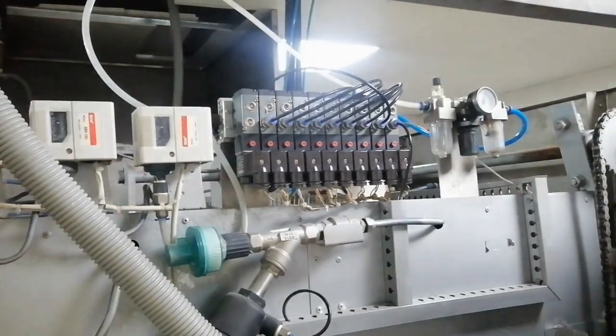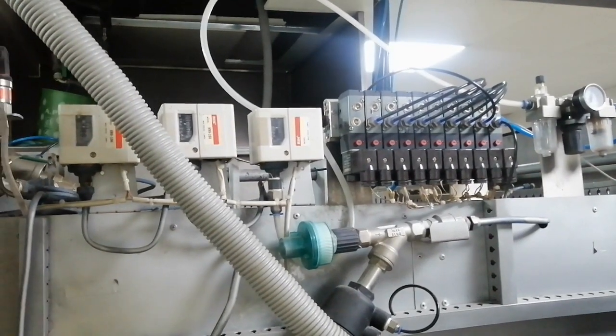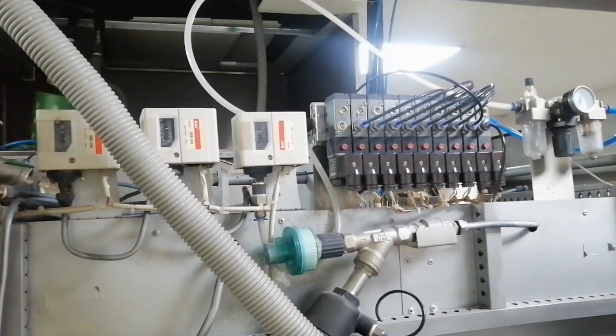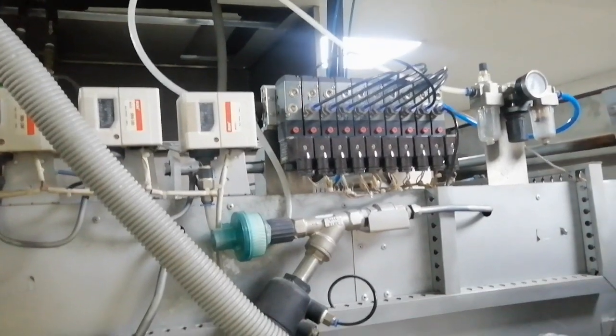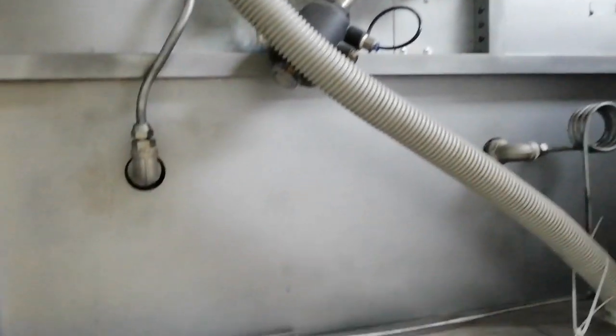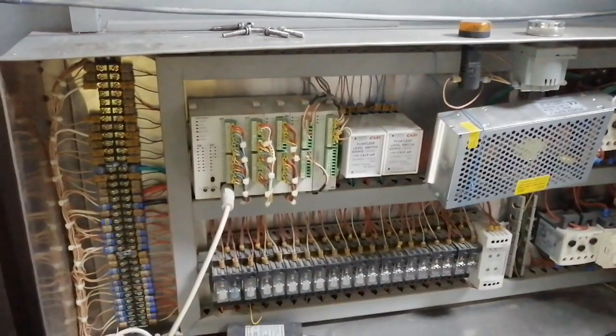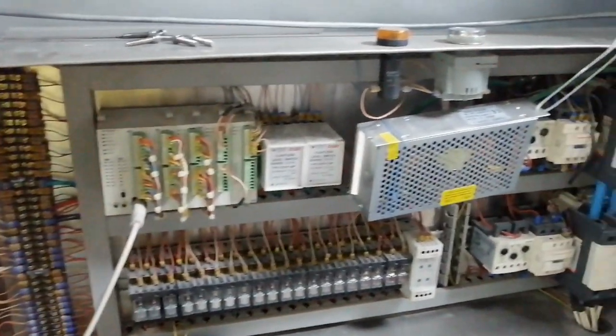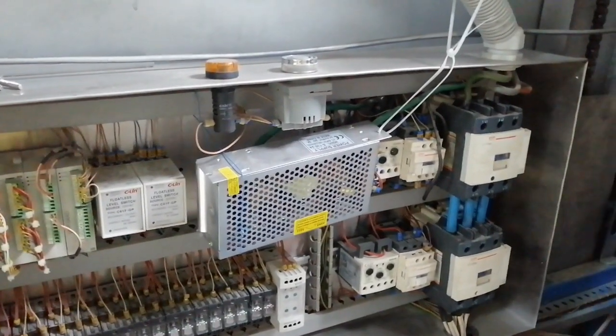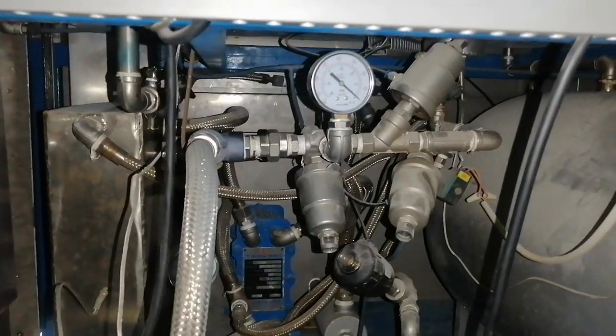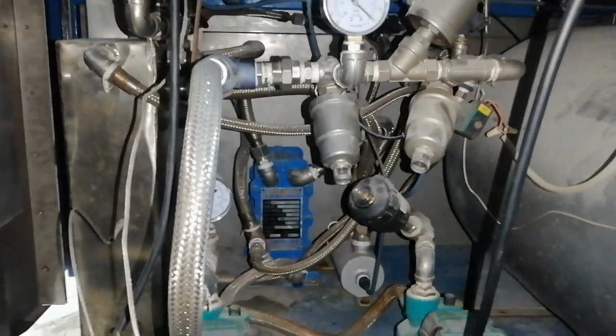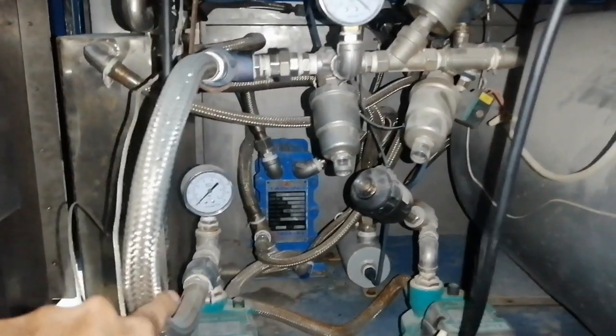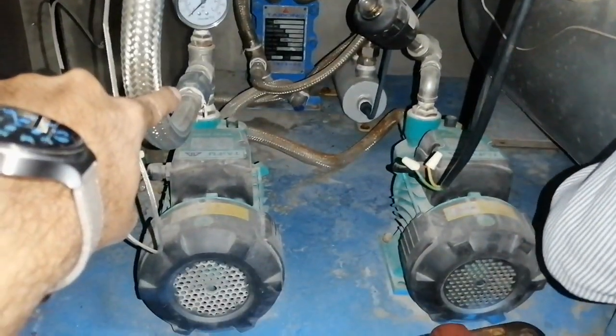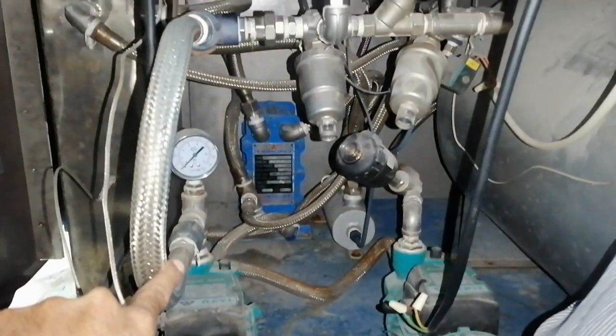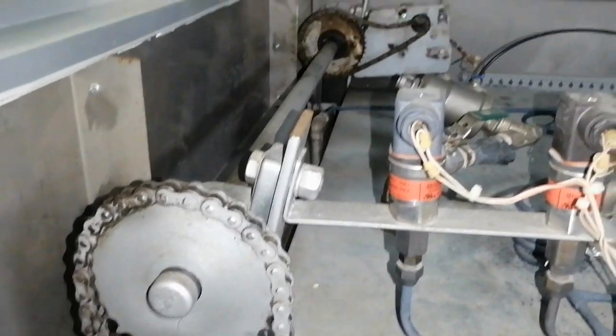So here is the internal structure of the steam sterilizer, where the different pneumatic switches, control switches, and safety switches are displayed. Here is the whole PLC system, relay system, power supplies, and other power switches as well. On the bottom side, here are the feeding pumps, pressure gauges, and safety valves to provide the chamber steam and water supply. Here is the door opening mechanism, which is operated by dual motors.